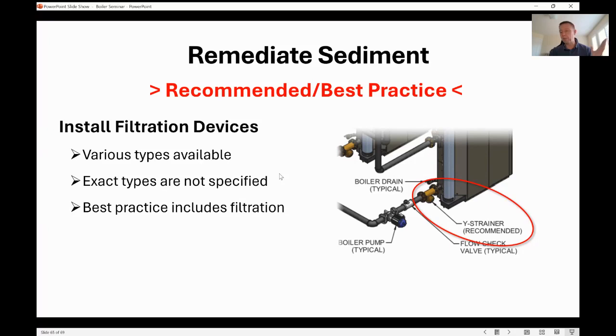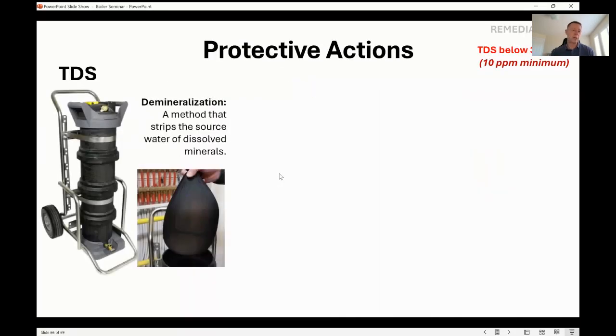I always recommend filtration devices, always, because if there's any crap in that system, it's a retrofit. You stir it up, it will end up in that boiler. So you want to prevent that from happening, because your brand new boiler could be a repurchase within months. Put in Y strainers. I recommend them.